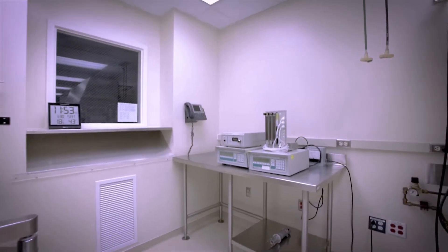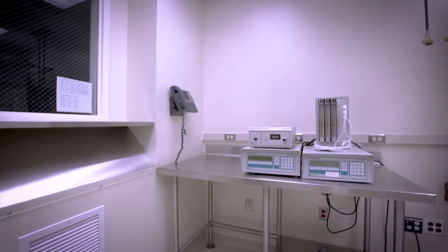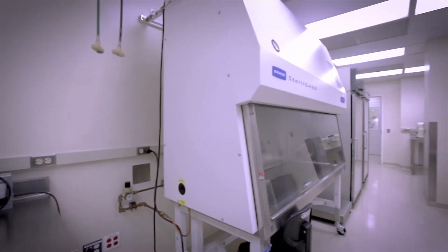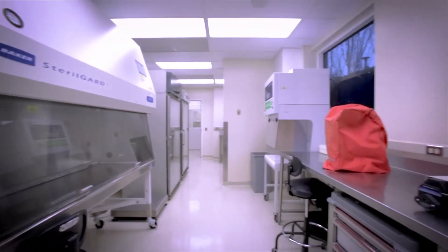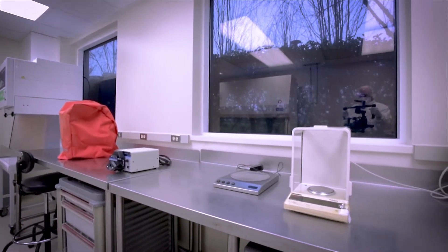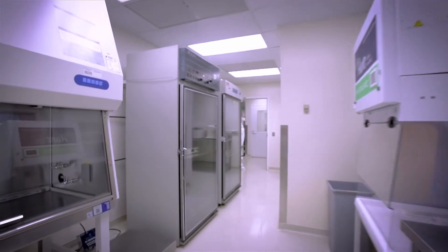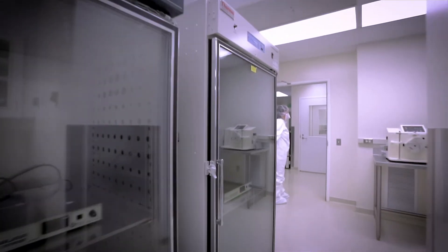Mammalian processes are run in our 110-liter stainless steel bioreactor using an Applikon 1030 controller. For mammalian processes, the maximum working volume is 85 liters. Lentivirus is produced using up to 20 1-liter cell stacks in our incubators using an adherent lentiviral platform. Upstream microbial production is not done in the standard GMP production suite. CD151 process development area is converted to GMP use and requires environmental monitoring, gowning, and access controls. The smaller 70-liter stainless steel vessel uses an Applikon 1010 controller with a working volume of around 55 liters.